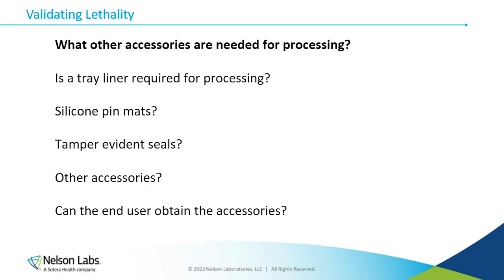We also need to look at accessories. Are we going to require a tray liner for processing? Do we need to include silicone pin mats? Do we need to validate with tamper evidence seals or any other accessories that might be required by the end user to properly process the device? And can those end users obtain those accessories?